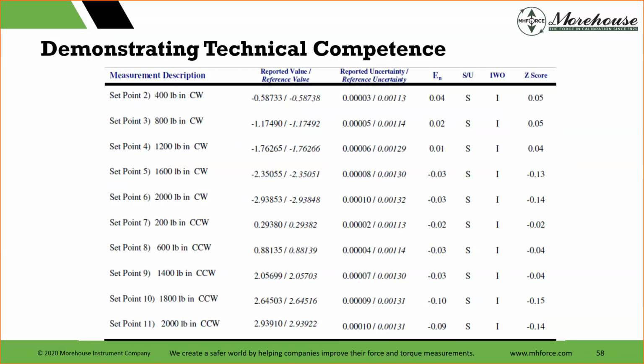And for those that answered the question, yes, this is Morehouse, like I said, the whole thing. We can calibrate your torque cells, which can quantify any additional errors in your system. You can run your own ILCs against a really, really well-known cell calibrated in that machine, and you can see how you're doing. If you run your own ILCs, we have a downloadable CMC calculation sheet that allows you to run ENs. You can run your own and see exactly where you are and what you need to improve. If your EN is over 1, you can decide to do things such as raise your uncertainty.